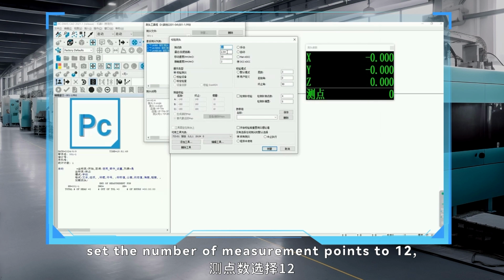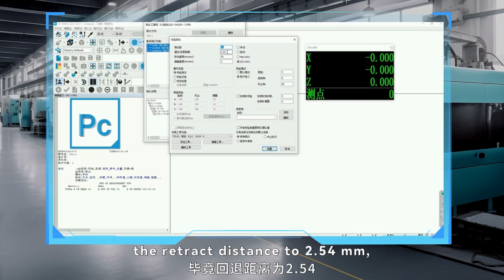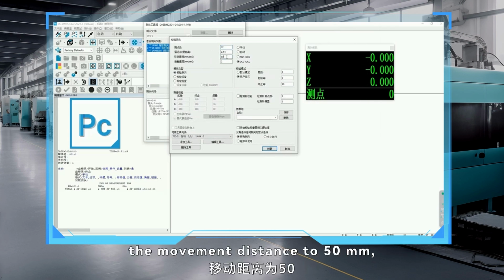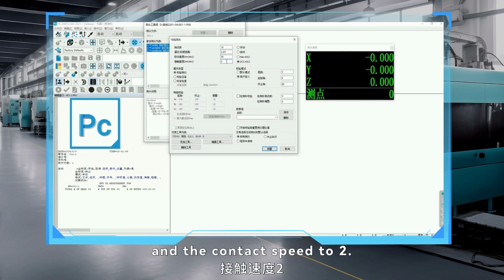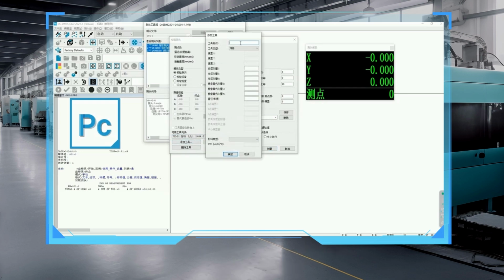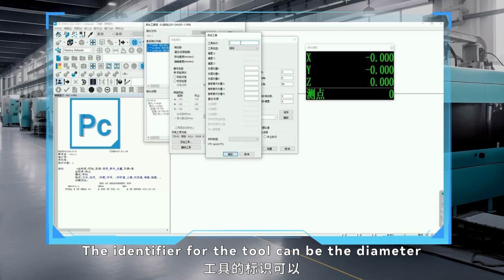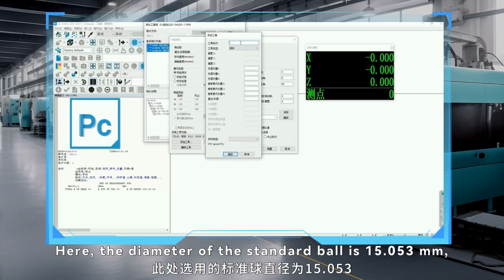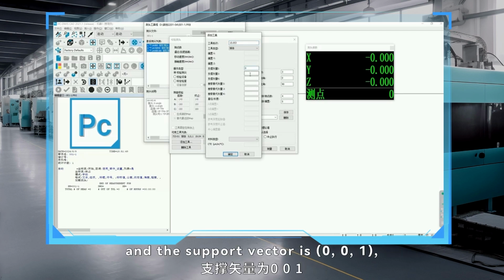Set the number of measurement points to 12, the retract distance to 2.54 millimeters, the movement distance to 50 millimeters, and the contact speed to 2. Choose the standard ball. The identifier for the tool can be the diameter of the standard ball. Here, the diameter of the standard ball is 15.053 millimeters, and the support vector is 0, 0, 1.